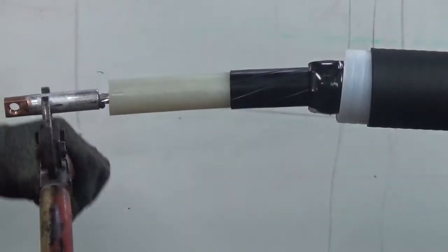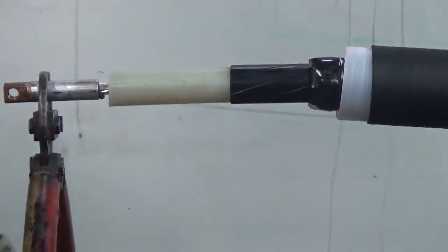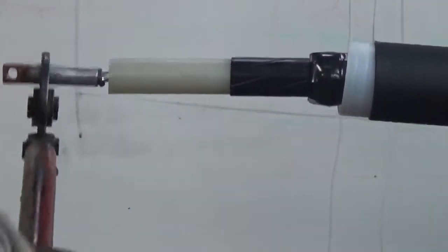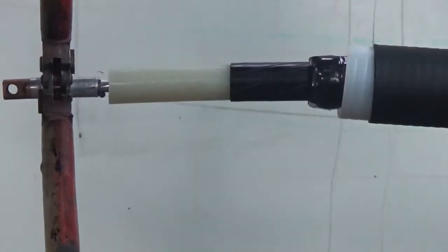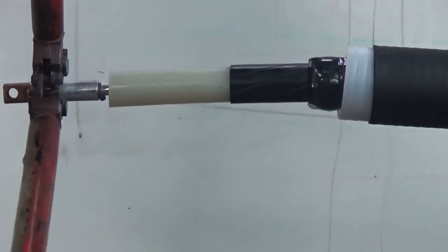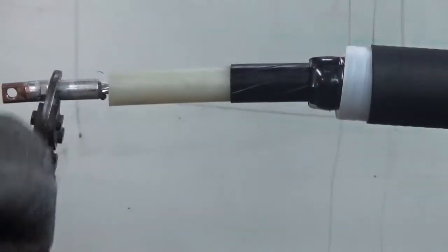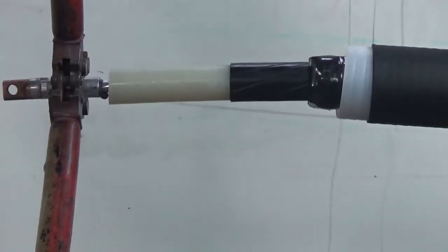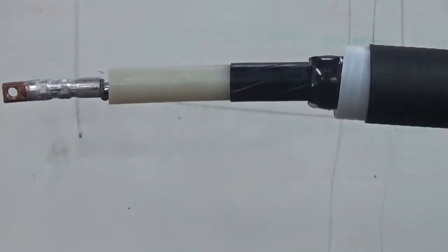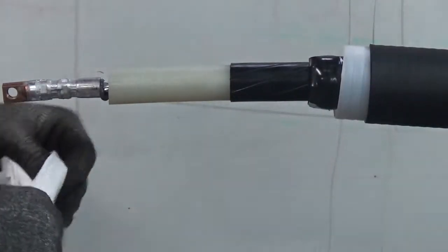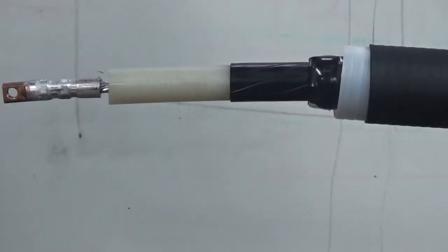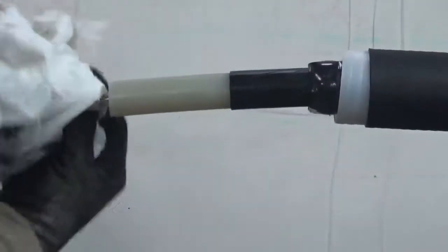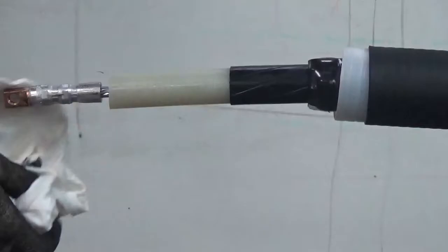Get your lug on, get it lined up proper, and on these you can use a little shotgun press. You want to rotate 90 degrees for every press. This lug, about 4 presses is good. If you start getting too much, it will start to bend over in a banana shape on you, which makes it hard to get your elbow to line up, and then to get the probe in there that needs to go inside the bushing.